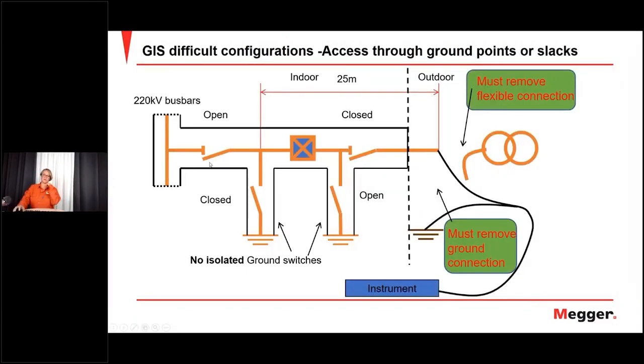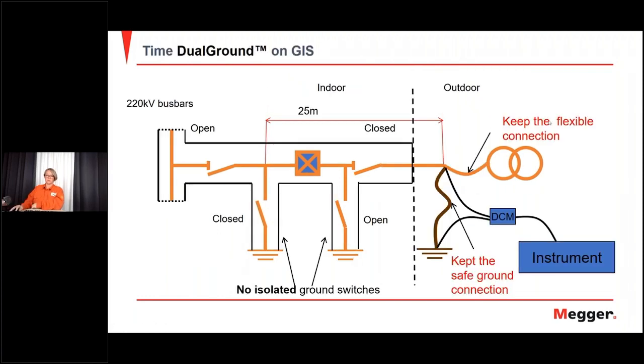So another configuration where you have the disconnector here, which can be closed, but you need to remove a slack to be able to measure the traditional way. But with dual ground, you can keep the connections and actually connect at the transformer or the slack and at the ground. And the circuit the instrument will find will be here. We have the ground through the closed earthing switch, measure the circuit breaker and through the closed disconnector. And you will keep the safe ground on both sides, both here and here, during the whole measurement. And no changes in the mounted details of the switchgear.